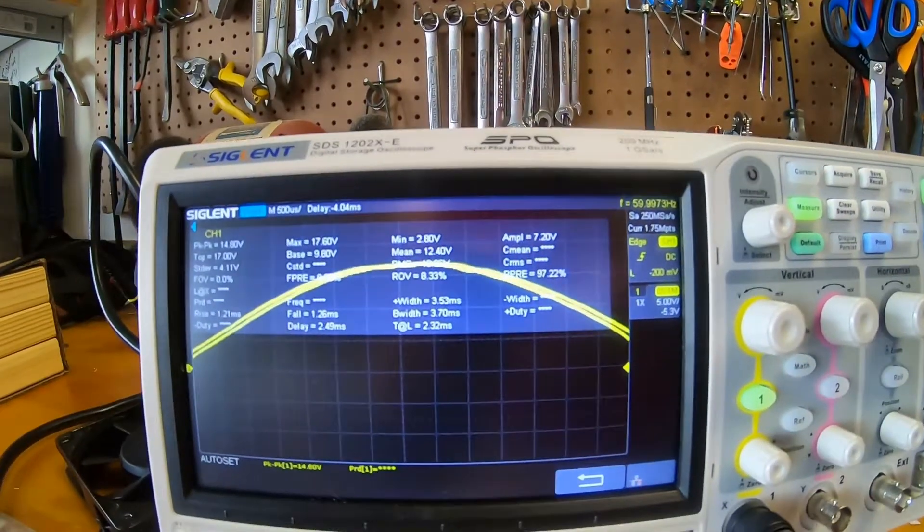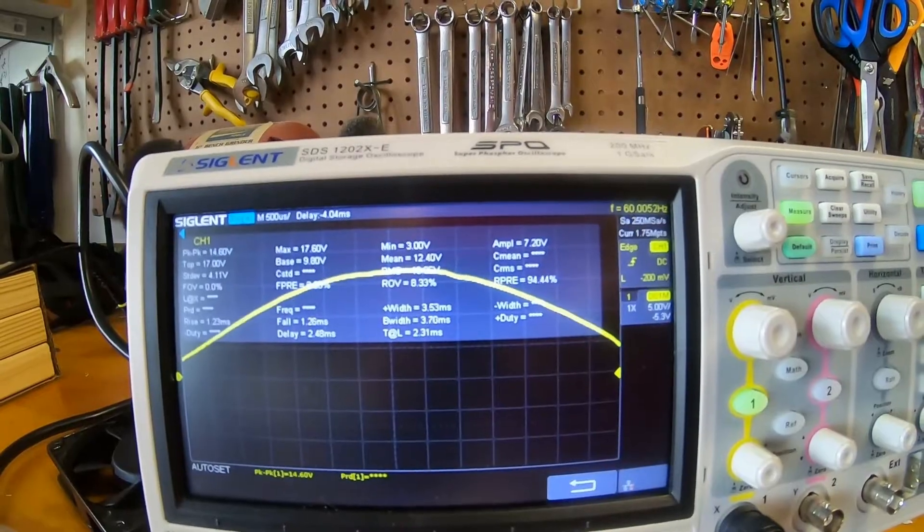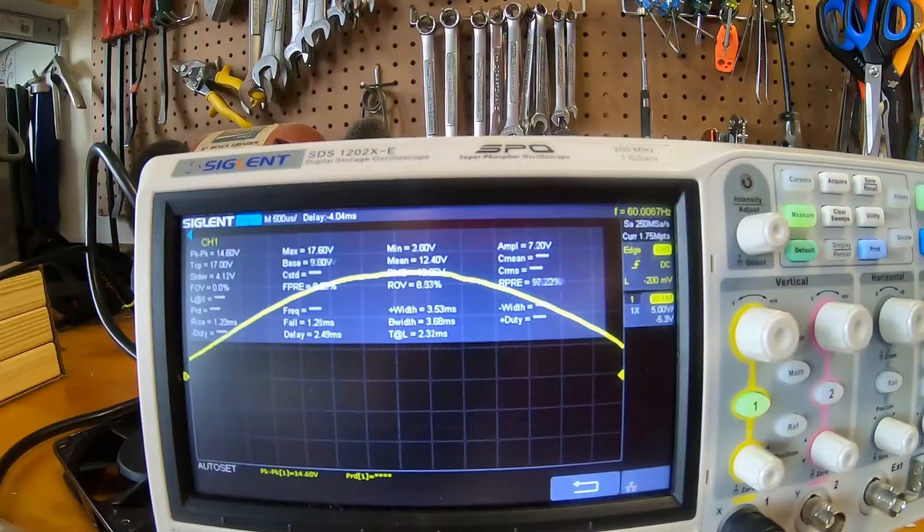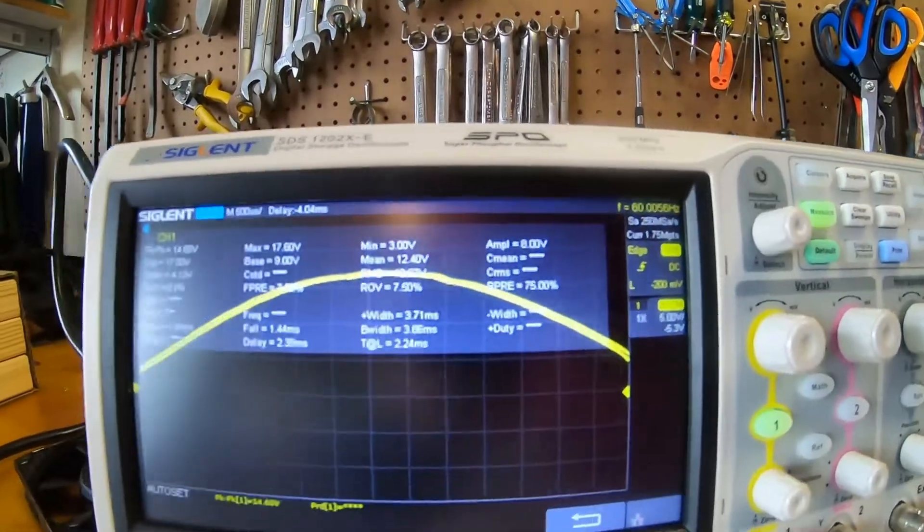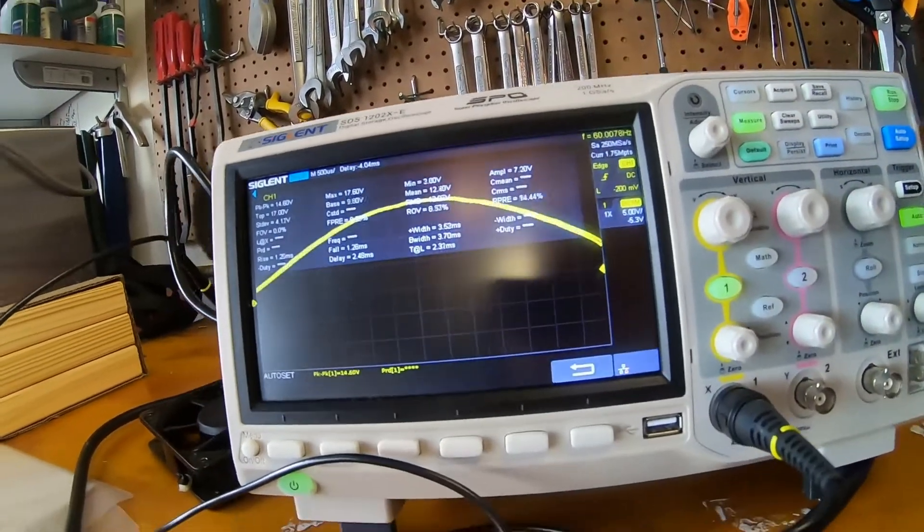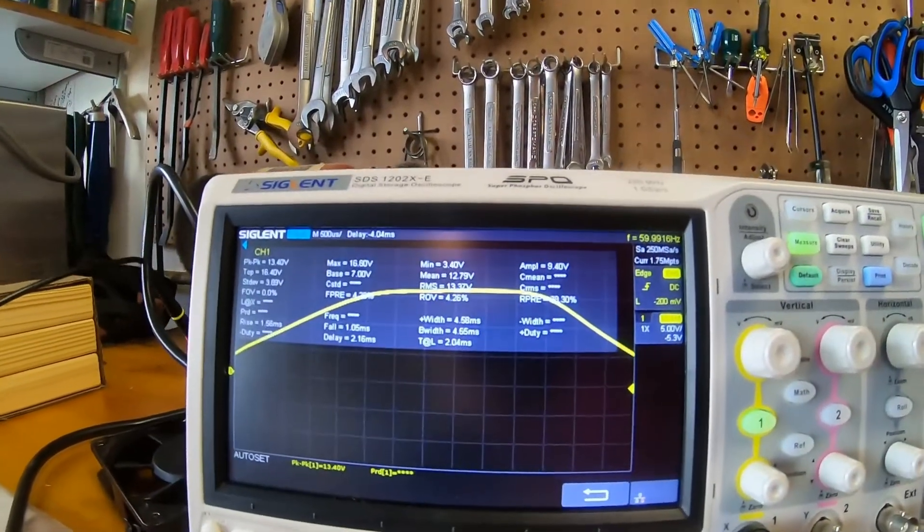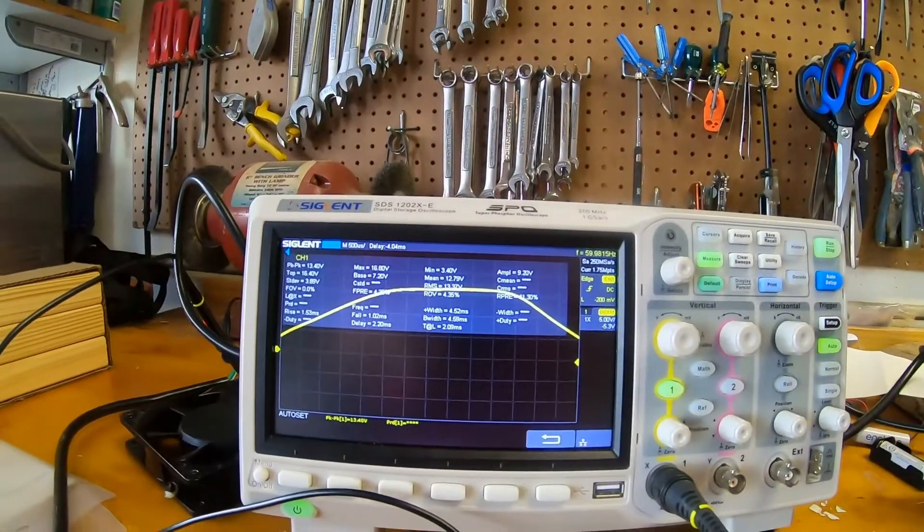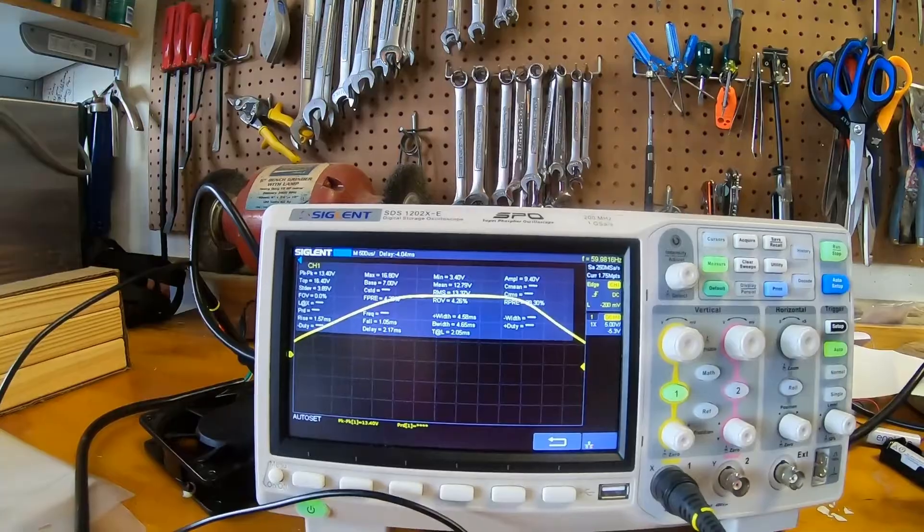Let's take a look at that when we were on battery power. To be honest with you, it actually looks a little bit better on battery power. It's pretty darn impressive. Again, that's battery. Utility. Notice the utility is a little bit flatter at the peak. Whereas on battery, it's a bit more round.